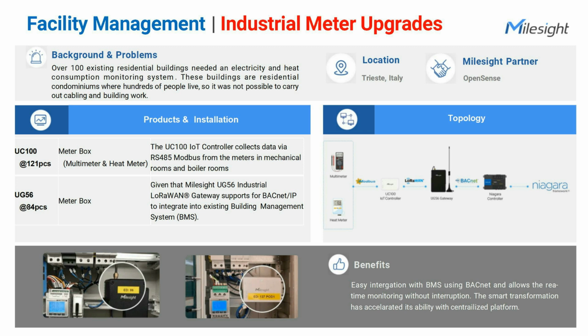So our partner, OpenSense, deployed over 100 units of UC100 controllers and 84 units of UG56 LoRaWAN gateways. The UC100 controllers collected data via Modbus from multimeters and heat meters, and the gateways support data integration into the building management system via supported BACnet to IP protocol.